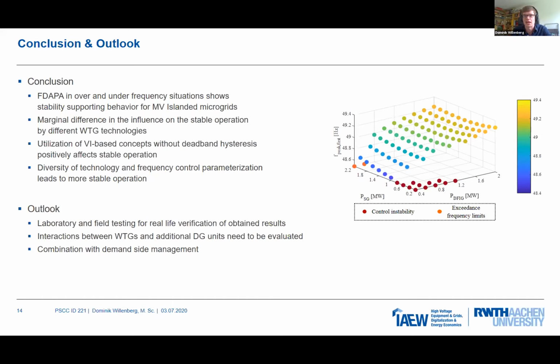What we also see is that if we have a really large or high infeed of active power by the synchronous generator, which is the orange dots here, really close to the operational limits of the synchronous generator, it is again kind of critical because it is not possible to flexibly increase the active power over a certain value. So here again we have a limitation, which then leads or may lead to an exceedance of the frequency limits. So yes, there is definitely an effect here. Yeah. Thank you for answering.